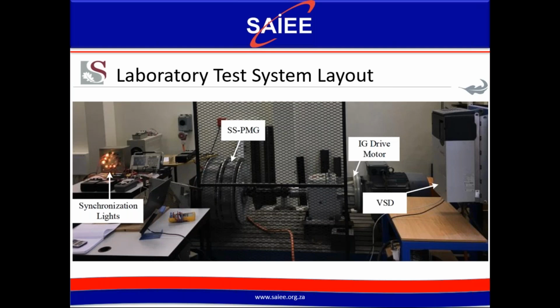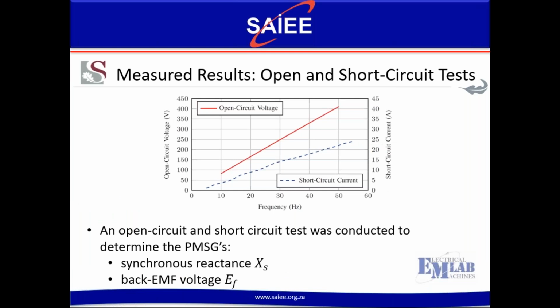Once grid connected, the voltage at the terminals of the generator can be varied by means of a variac, and the supply power to the generator can be varied by changing the speed reference voltage given to the induction motor. However, before any grid connection tests can be conducted, an indication of what this particular generator's synchronous reactance and back EMF voltage values are needs to be determined. In order to do that, an open circuit and short circuit test was conducted.